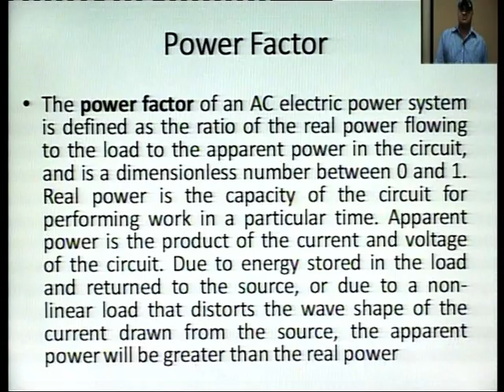Due to energy stored in the load and returned to the source, or due to a non-linear load that distorts the wave shape of the current drawn from the source, the apparent power will be greater than the real power. The ratio of real power to apparent power is called the power factor, or we can say the cosine of the angle between the voltage and current is the power factor. A load with a low power factor draws more current than a load with a high power factor for the same amount of useful power transferred.